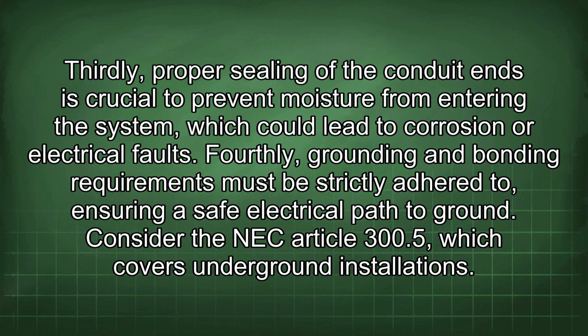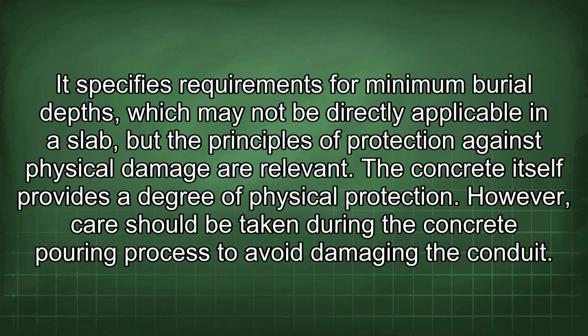Thirdly, proper sealing of the conduit ends is crucial to prevent moisture from entering the system, which could lead to corrosion or electrical faults. Fourthly, grounding and bonding requirements must be strictly adhered to, ensuring a safe electrical path to ground. Consider the NEC Article 300.5, which covers underground installations. It specifies requirements for minimum burial depths, which may not be directly applicable in a slab, but the principles of protection against physical damage are relevant.